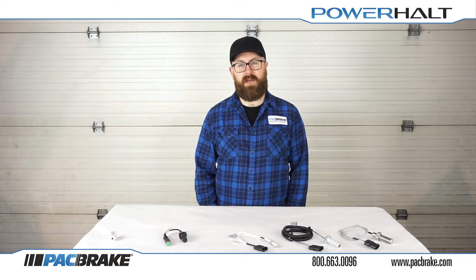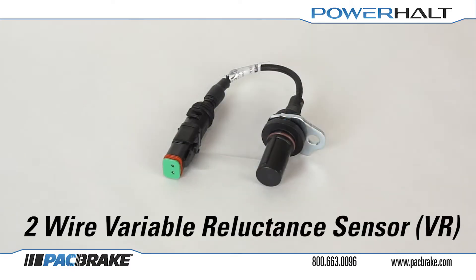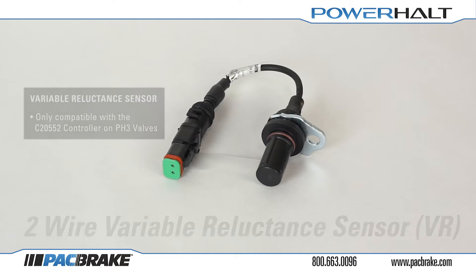Pacbrake offers two different types of magnetic pickup speed sensors which could be behind these issues: the 3-wire Hall Effect type sensor and the 2-wire Variable Reluctance or VR type sensor. Note that the VR sensor is only compatible with the C20552 controller on the PH3 shutoff valves. Identify which sensor you have before proceeding.